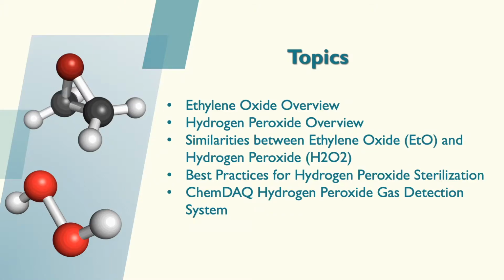Both ethylene oxide and hydrogen peroxide are there to kill all life. These are used so we can ensure proper sterilization for all your medical devices. The vapor concentration inside a gas sterilizer would kill anything instantly if you were inside.